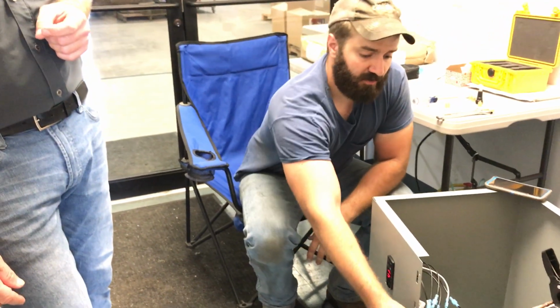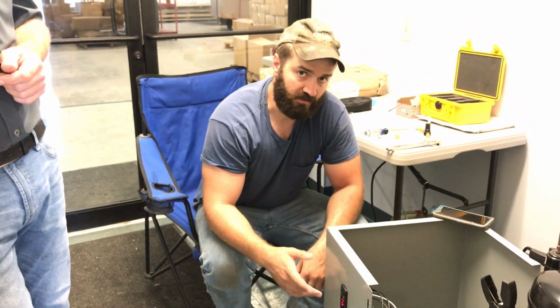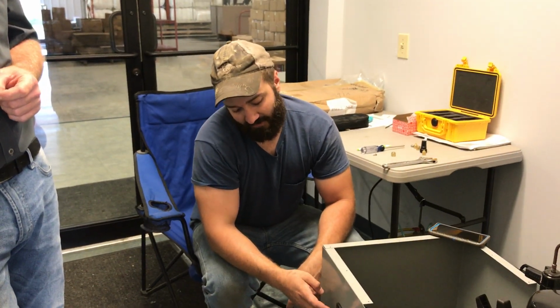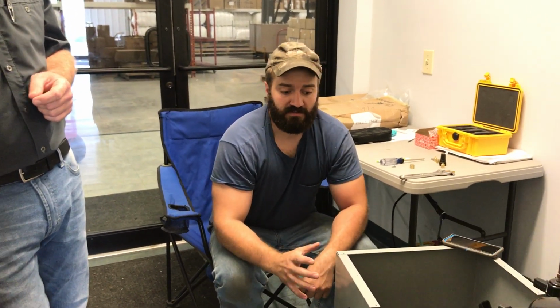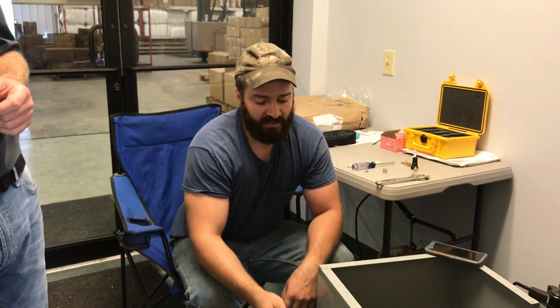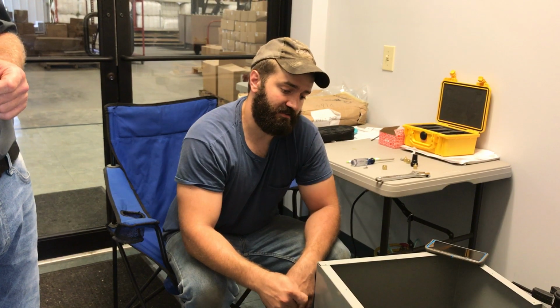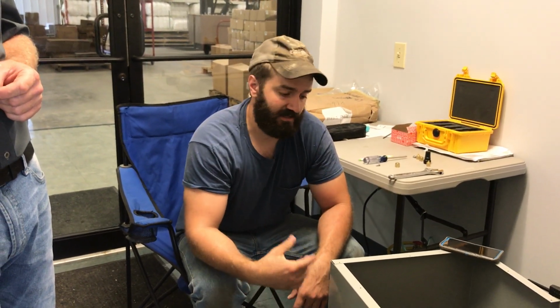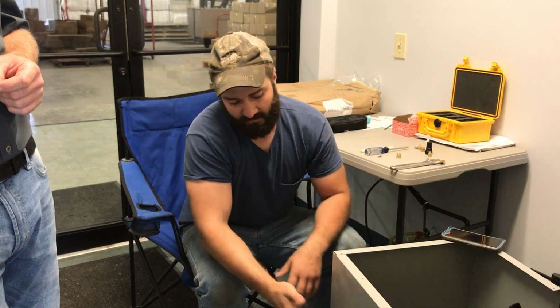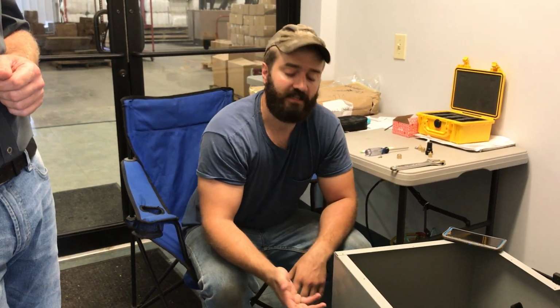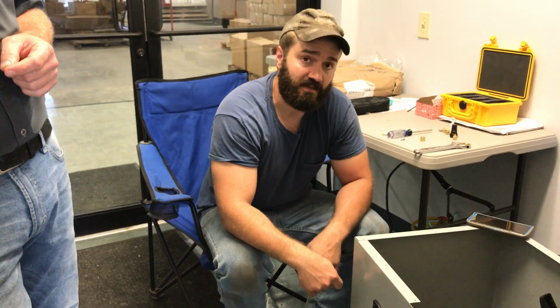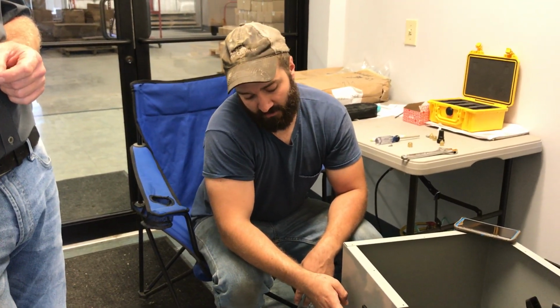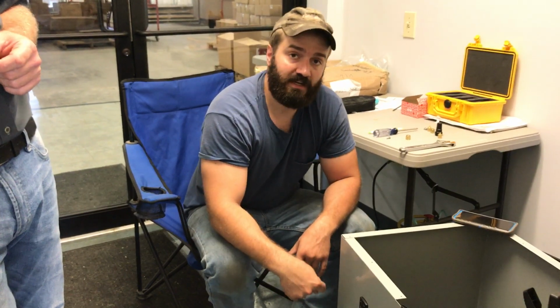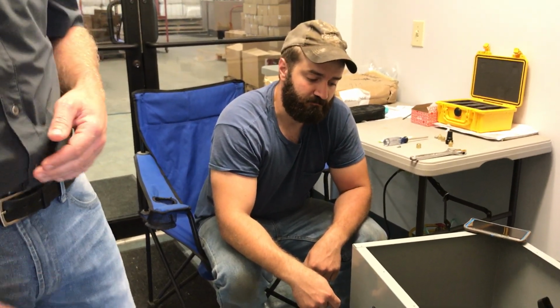The other probe is embedded in the evaporator coil, and the way we have it set, it acts as a defrost thermostat. It only monitors the coil temperature, and once it gets low enough that the coil is freezing up, it goes into defrost mode so it doesn't just continue to run. Say it's a hot day, you open the door, you hang an animal in it, and it runs longer than typical—if it ices up, it'll go into defrost mode. So it cycles on both cabinet temperature and coil temperature if needed.